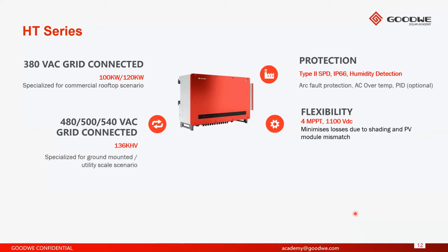All three inverters come with type 2 surge protection. A type 1 surge protection is also available as an option, but it cannot be retrofitted, so it must be ordered direct from the factory. We have increased the protection rating on this range of inverters. So the MT, as you saw, was IP65, and the HT is an IP66 inverter. We have also humidity detection as a standard, and as an option, we do offer the possibility of having an arc fault protection, an AC over temperature detector on the AC output terminal, and we also have PID protection as well. So that's potential induced degradation on the panels.